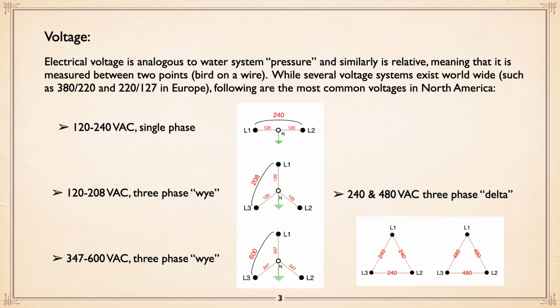Something that's not seen much in the US, but quite common in Canada, particularly in British Columbia, is 347/600, which again is a three-phase Y connection. And again, three hots and a neutral, except between the hots is 600 volt. And if you connect with three of them, you have 600 volt three phase. Any one of those hots to neutral is 347 volt.